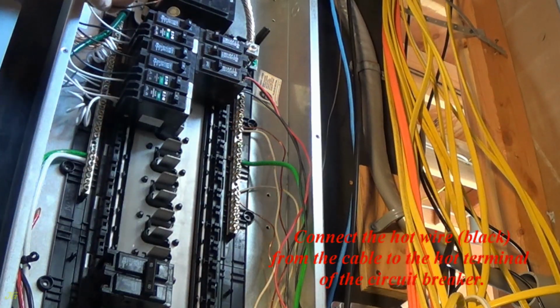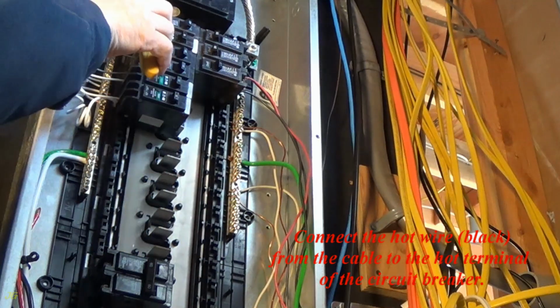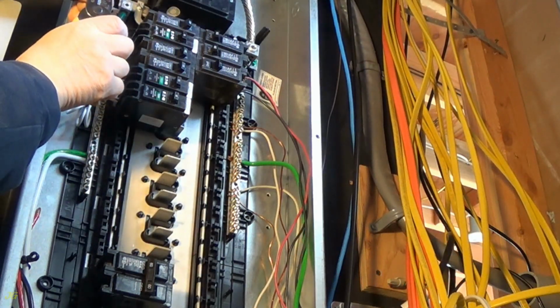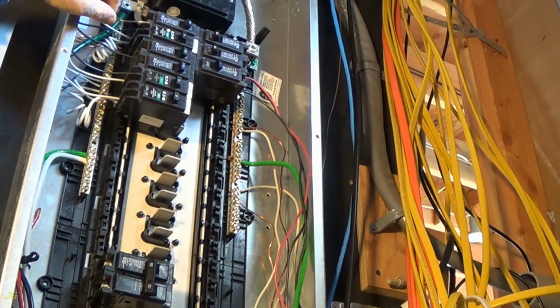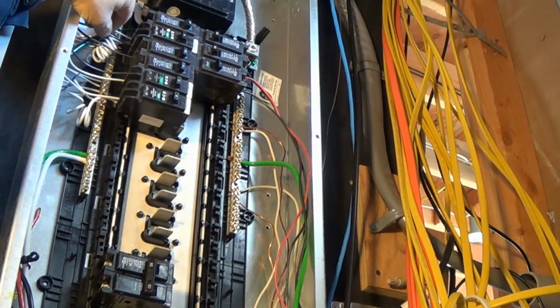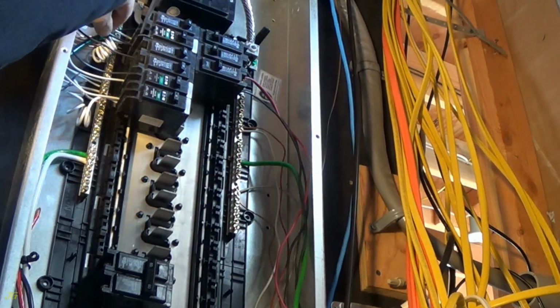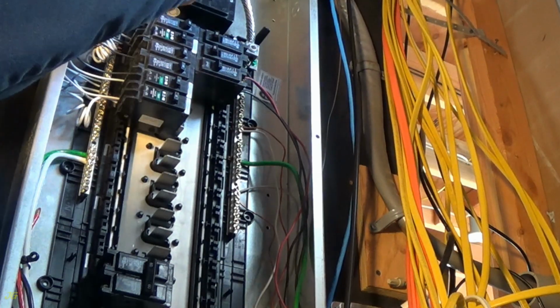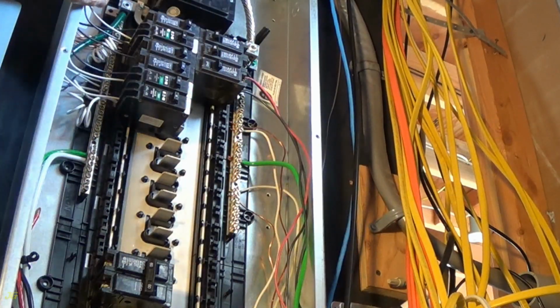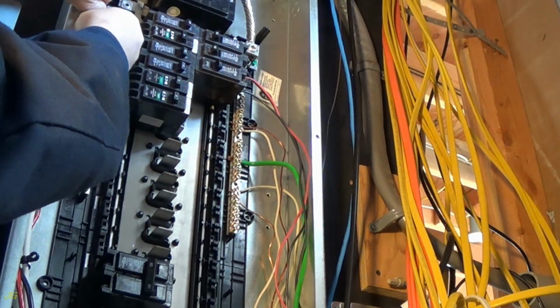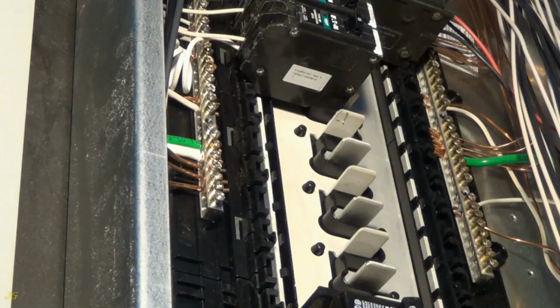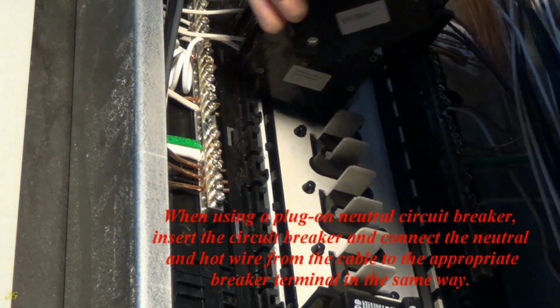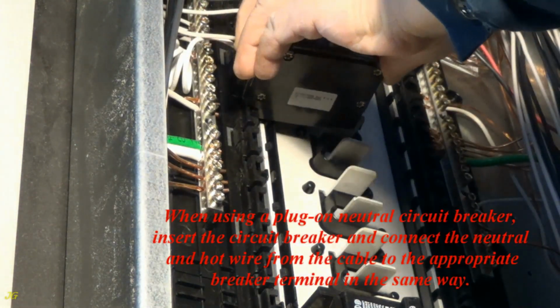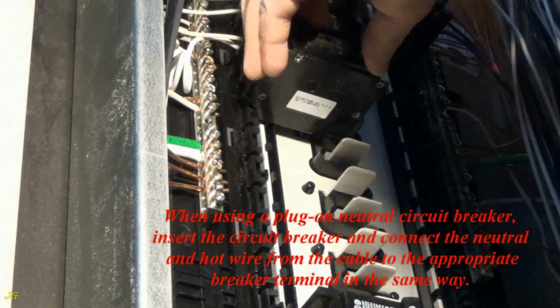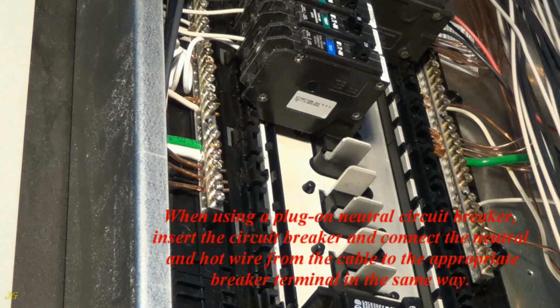Connect the hot wire, black, from the cable to the hot terminal of the circuit breaker. When using a plug on neutral circuit breaker, insert the circuit breaker and connect the neutral and hot wire from the cable to the appropriate breaker terminal in the same way.